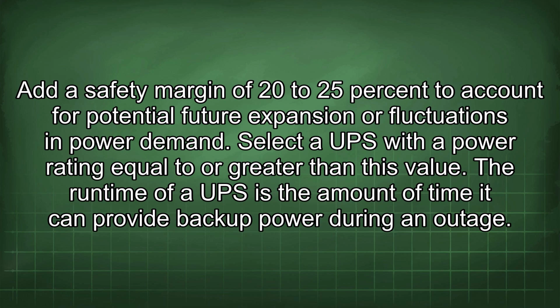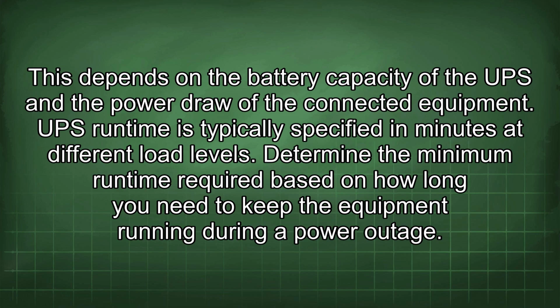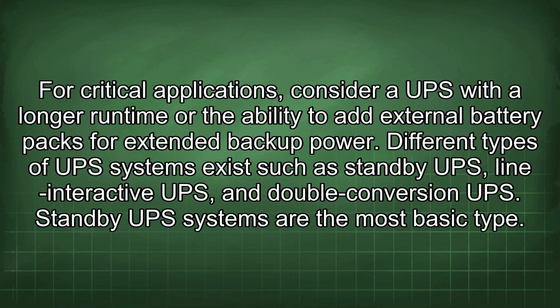The runtime of a UPS is the amount of time it can provide backup power during an outage. This depends on the battery capacity of the UPS and the power draw of the connected equipment. The UPS runtime is typically specified in minutes at different load levels. Determine the minimum runtime required based on how long you need to keep the equipment running during a power outage. For critical applications, consider a UPS with a longer runtime or the ability to add external battery packs for extended backup power. Different types of UPS systems exist, such as standby UPS, line interactive UPS, and double conversion UPS.